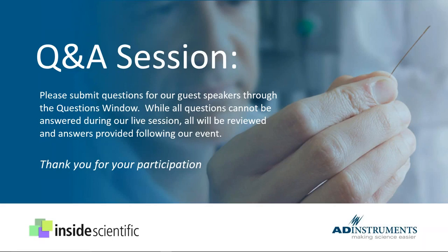Sure. The alpha and the stroke volume, they're essentially doing the same thing. If you derive your alpha from a cuvette, the cuvette will give you the same value each time, the only variability being the resistivity of the solution and the placement of the catheter. The stroke volume has two aspects to it: one is at steady state, using whatever reference measure you need, and one is during a preload occlusion. Theoretically, those values at steady state and during the preload occlusion should be the same.